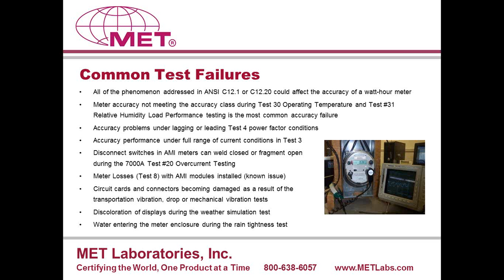Again, some more of the common test failures here. Any of the 38 tests in the standard could obviously affect the product and could cause a failure. But again, the temperature, the operating temperature, the humidity test, many times we'll see that be a problem. And typically it's at the high points of that, at plus 70 or maybe plus 85 with 90% humidity, or at the low end at minus 30. Accuracy problems under power factor conditions could be an issue. The performance for accuracy under the full range of tests, not just at test amps or at light load, but light load up to the maximum current that the meter is spec to, could be an issue.